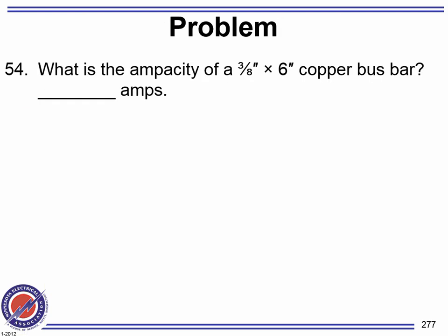The last one related to ampacity was on my master's exam when I took it. How much amperage can a copper bus carry? A bus bar, you've probably seen them. The length can be anything you want it to be, and the width and the depth. There you go. So they're giving me a 6 by 3/8. The key point for this one, guys: if it was copper, a square inch of it can carry 1,000 amps. If it's aluminum, a square inch of it can carry 800 amps.